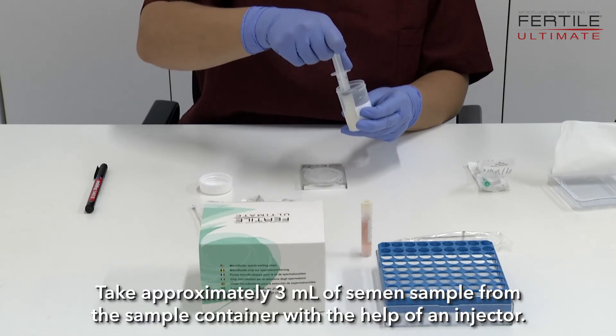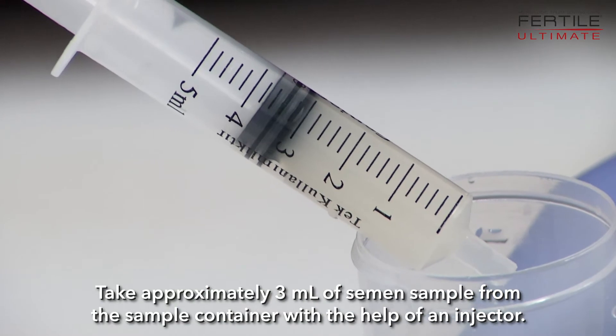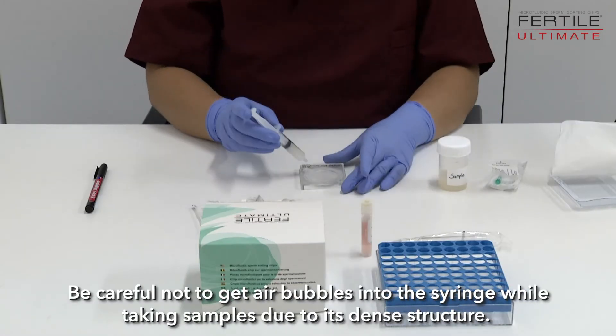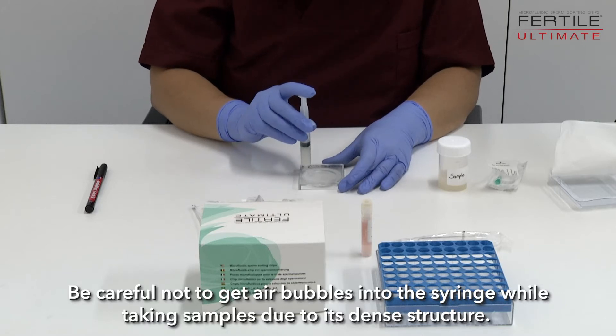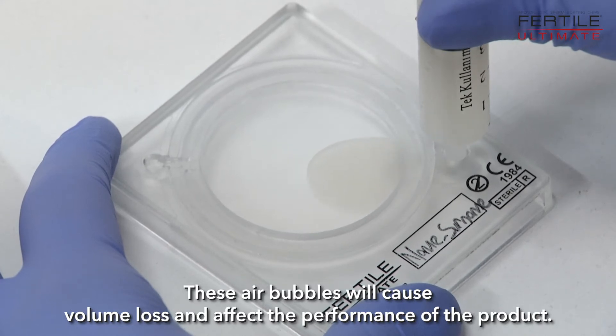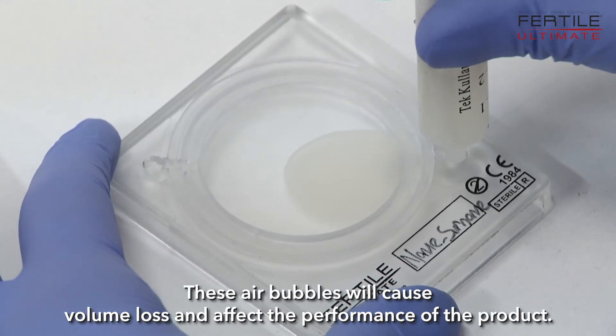Take approximately 3 mL of semen sample from the sample container using a syringe. Be careful not to introduce air bubbles while drawing the sample, as its dense structure makes this likely. Air bubbles will cause volume loss and affect the performance of the product.